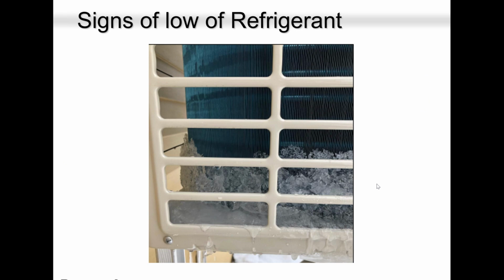Look at this unit. This unit was low on refrigerant, about 8 to 9 ounces less. And guess what? It wasn't defrosting completely. This unit is a 9000 XC. It has a base pan heater, but it didn't help much because the defrost cycle was not strong enough. And it was not strong enough because there was not enough juice. There was not enough refrigerant to melt all of this completely. So keep in mind, enough refrigerant is always important.